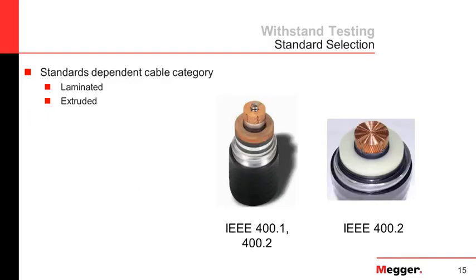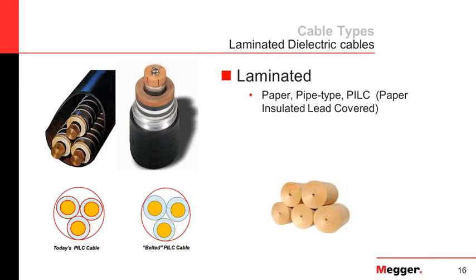There is some confusion about which standard to use for DC withstand testing, and this depends on cable category. There are two main categories: laminated cables and extruded type cables. Laminated cables are your paper cables, pipe type cables, and PILC cables — paper-insulated lead-covered cables — where the insulation is made of paper impregnated with oil for dielectric strength. Extruded cables are your EPR and XLPE cables.